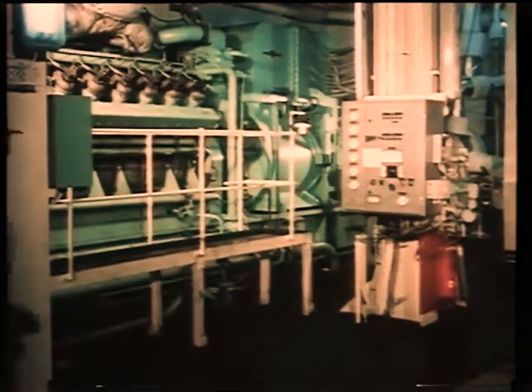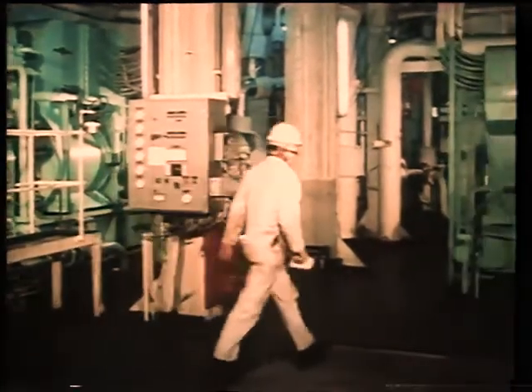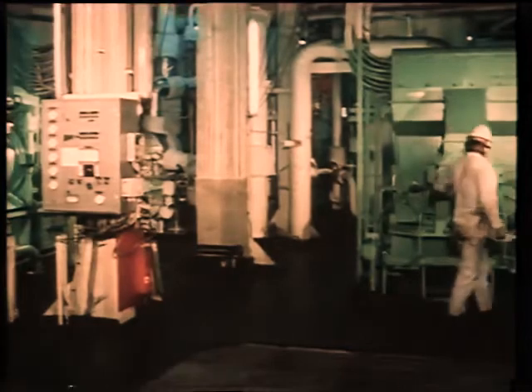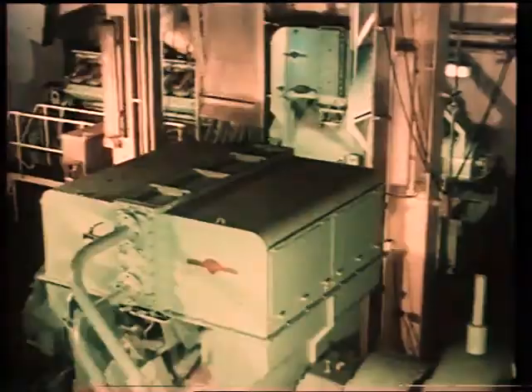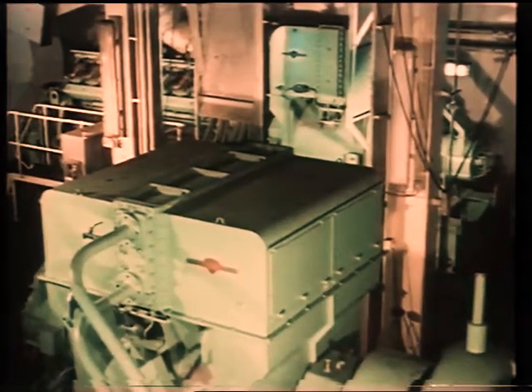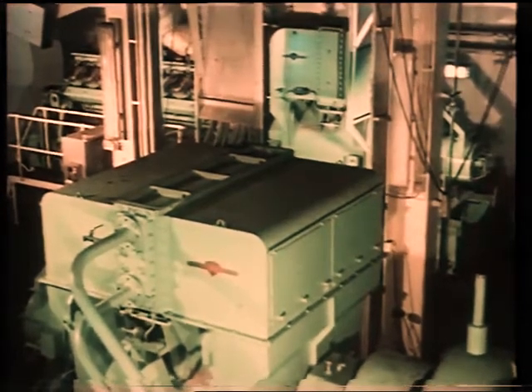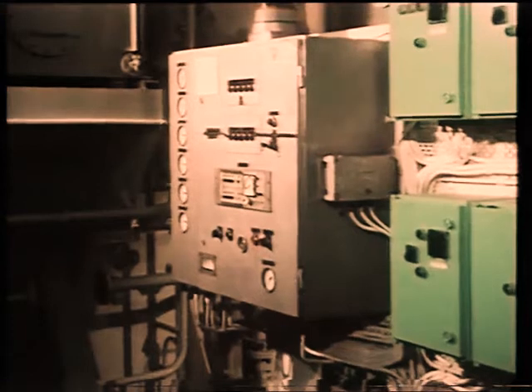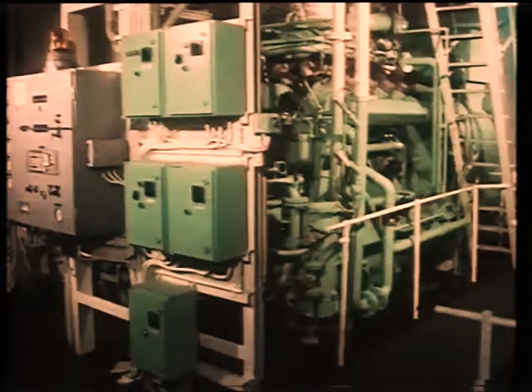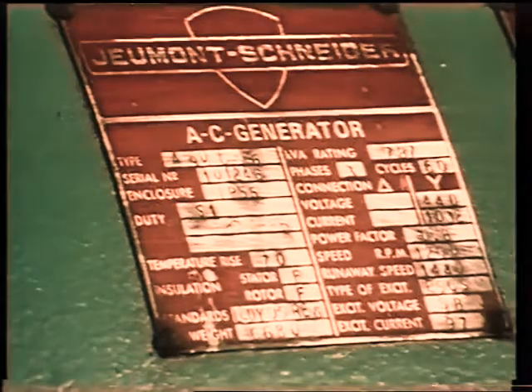Under normal conditions, generated power on board ship is supplied by one or more main alternators and one or more auxiliary or standby alternators, depending on the power needs of a vessel. These alternators may be driven by steam turbines or diesel engines, although at least one of these should be driven by diesel power in any scheme. Should the normal power supply fail for any reason, an emergency diesel alternator is started up automatically or manually to provide power and lighting for all essential services on board ship.